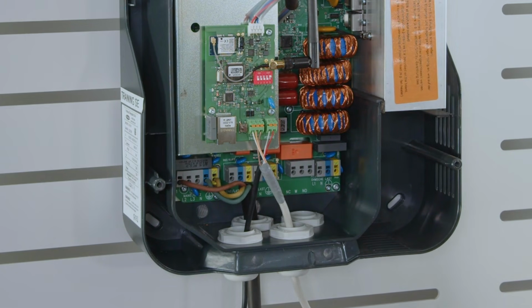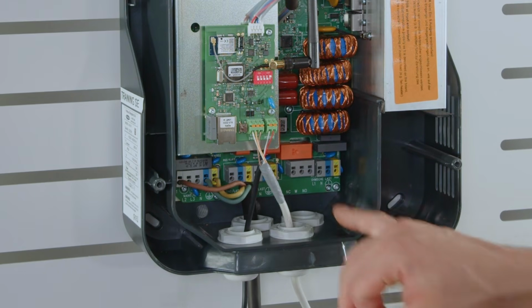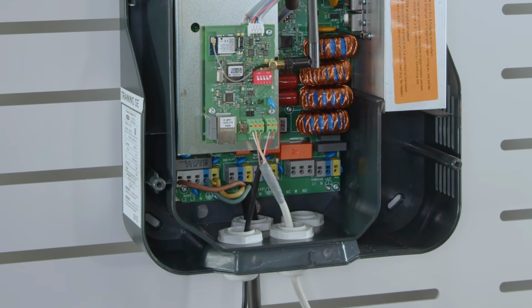Right, and between L1 and L2 we also have this multifunctional relay contact, which also gives you a little bit more possibilities, let's say. One would be to use up to 2 heating rods, which is possible as we have heard, and this one plays a major role in it. We see later on how. Or it would also give you the opportunity to switch on a smart grid ready heat pump, for example. And there we also use this plug. But more on that later in the commissioning.